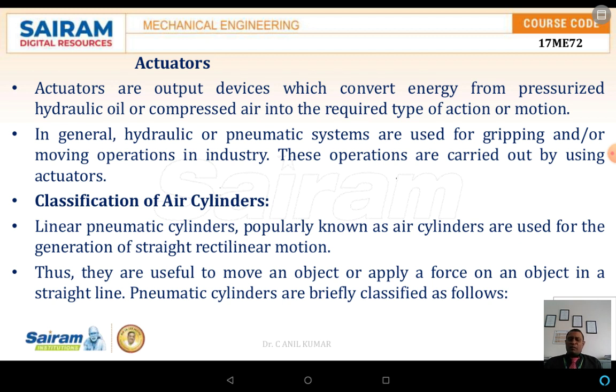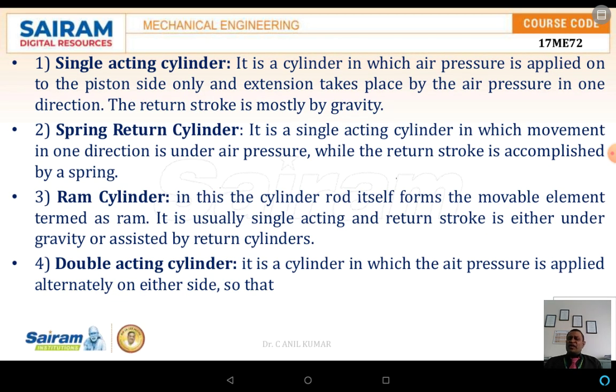Pneumatic cylinders are basically classified as follows. The first one is the single acting cylinder, which is a basic cylinder used in most applications. The second one is the spring return cylinder, where movement is in one direction by means of air pressure or hydraulic pressure, while the return stroke is accomplished by means of a spring. In the case of the single acting cylinder, there is no spring, so the reverse stroke is done by using gravity itself.